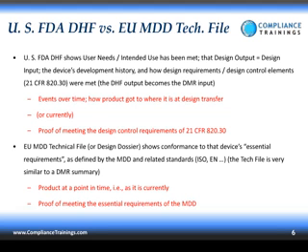The FDA's design history file is designed to prove compliance to design control during the development stage, from a start date that is selected by the company. We'll talk about that later. Now that's different from the European Union's Medical Device Directive technical file. There you're working with a notified body that you contract with. They're the ones that audit that technical file to make sure it's complete and that it's on file with the various countries in which you ship your product that have CE marking on your product. The technical file is for certain classes of product, and then, of course, the design dossier for Class 3. And we'll talk about the difference in classification as well.